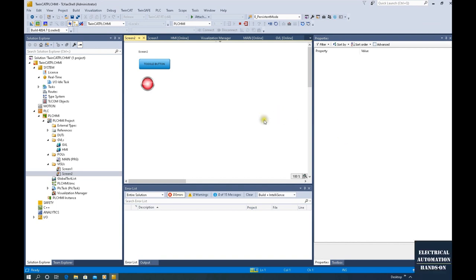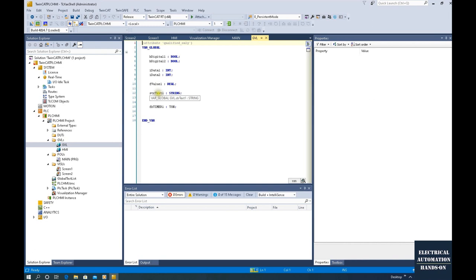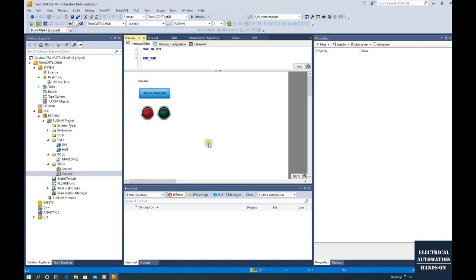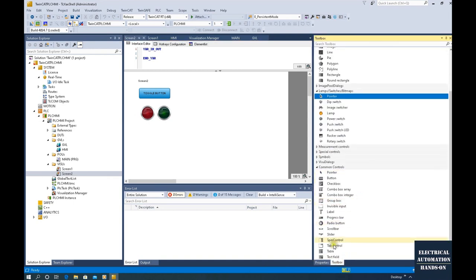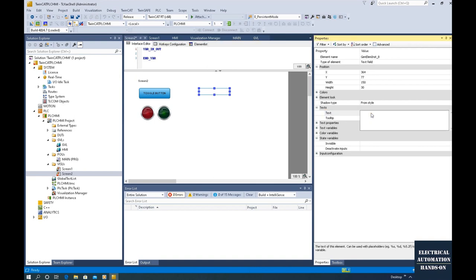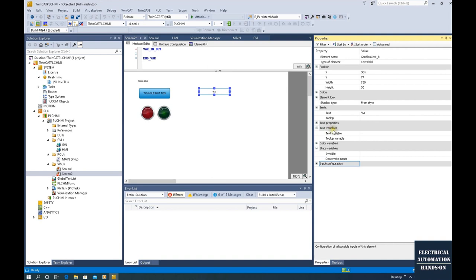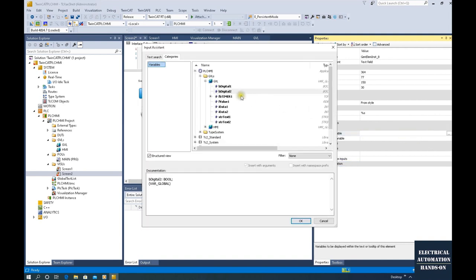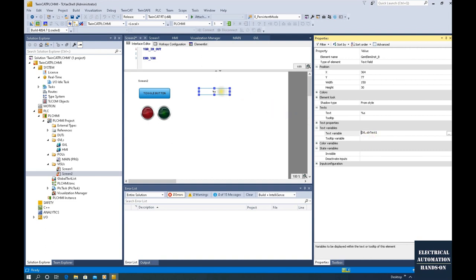Next, I will put another text field to show the string. Let me log out first. In the GVL, I will use one text field and show string test one. Let's go to Screen 2 and connect string test one. Come to the toolbox and drag one text field. To quickly review: for showing an integer, type in percent-i; for showing a float, type in percent-f; and for showing a string, use the format percent-s. As the text variable, we connect to that tag — string test one.